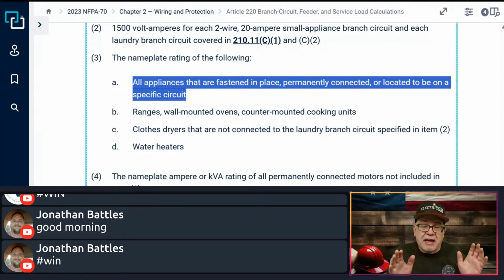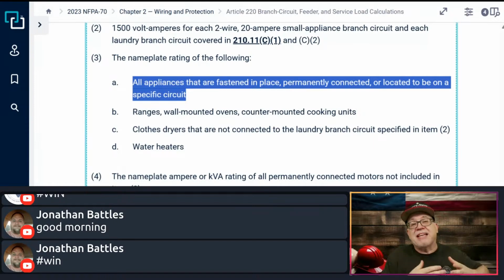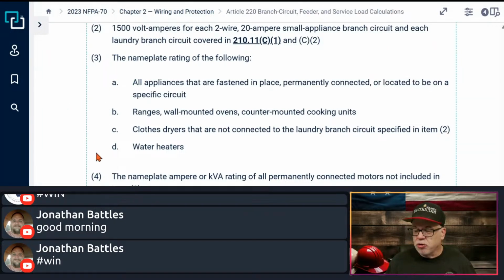That doesn't mean it's not an appliance. It just means that it's specifically excluded from that list. And that's why they did that, to remind you that, yeah, they know it's an appliance. We just don't want it added to this list when you're doing the standard method under 220.53, right? That's the reason they say that. They make it very clear, but it is most certainly qualifying as an appliance. A lot of people get confused with that, but we've set that record straight.